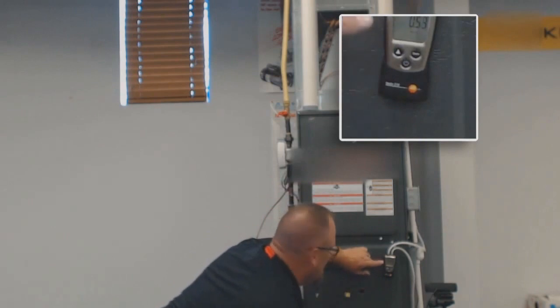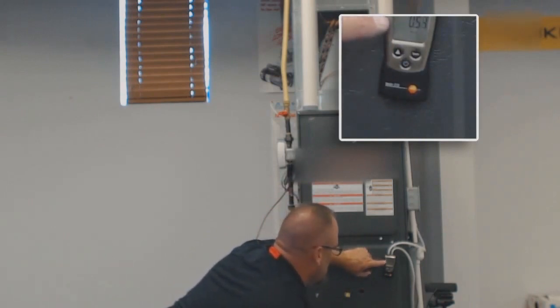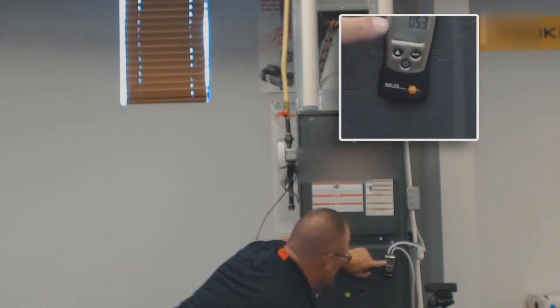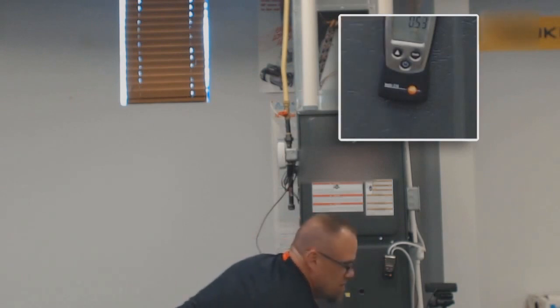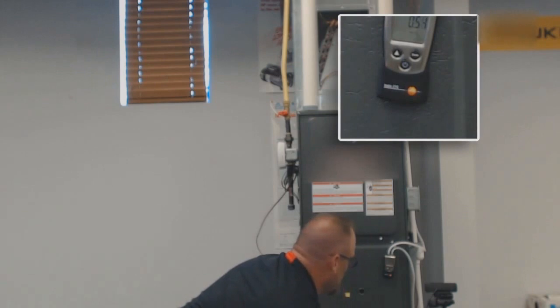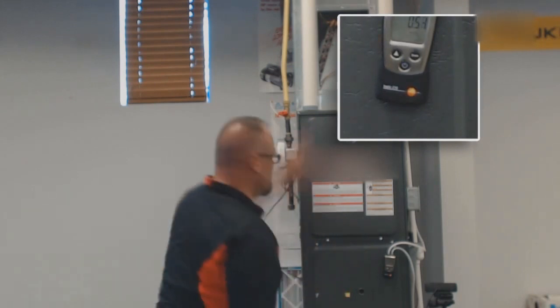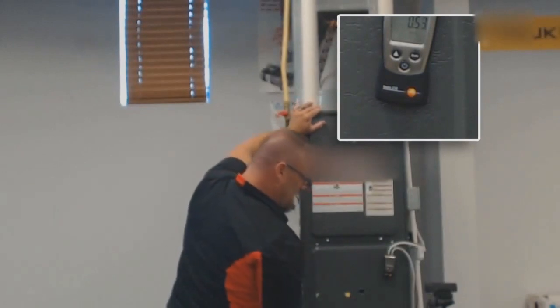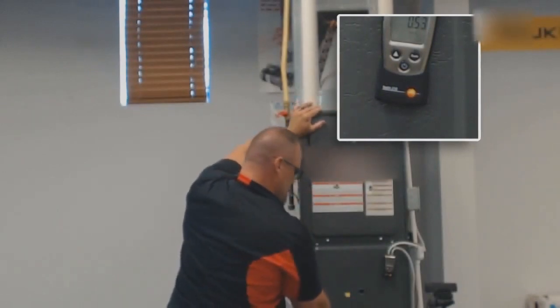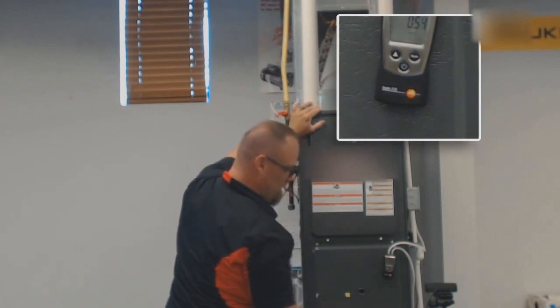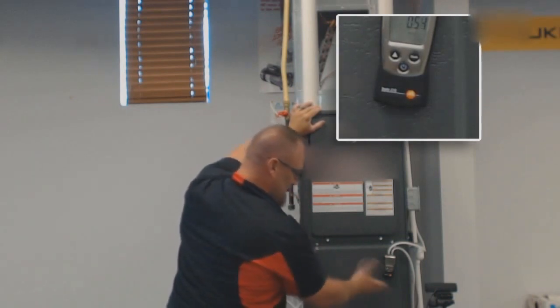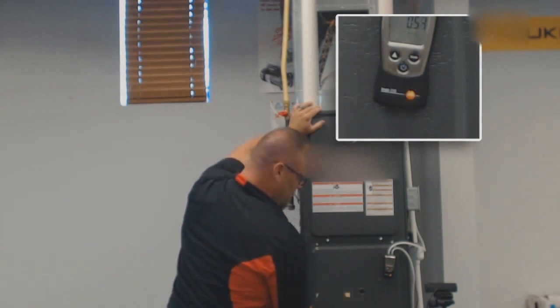As you can see, that definitely made an impact on our manometer. We went up a little bit. Now remember, this filter is brand new. There's no dirt on it. As it gets dirty, the more restrictive it's going to get, and it'll get dirty quicker. The fiberglass filters that we were just looking at won't hardly catch enough stuff that it'll get stopped up within the 30-day time frame that you're going to leave that thing in there.